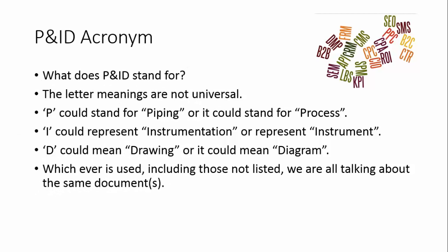P&ID is an acronym, and there's no real universal standard for what P&ID actually represents, although there are accepted phrases. First of all, the P usually will stand for piping or process. Those are the two most common terms that you'll use for the P. The I represents instrumentation or just instrument, and the D could mean either drawing or diagram. So P&ID can be piping and instrumentation diagrams. It could be process and instrumentation diagrams. It could be piping and instrument drawings. So no matter what the person is saying or how it is being talked about, they're exactly the same documents.